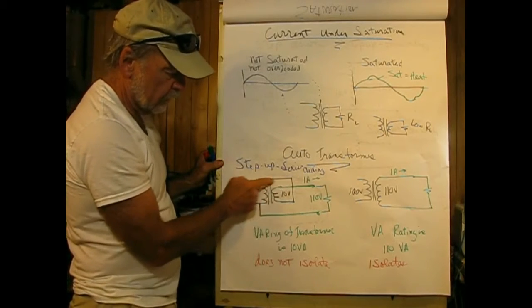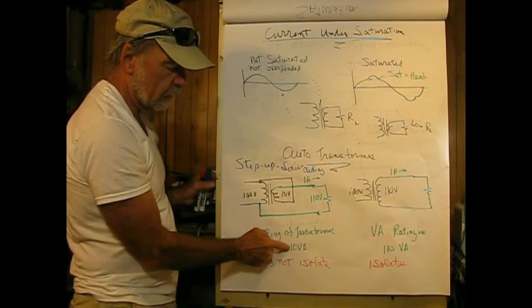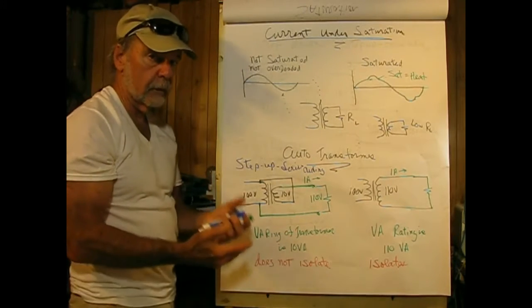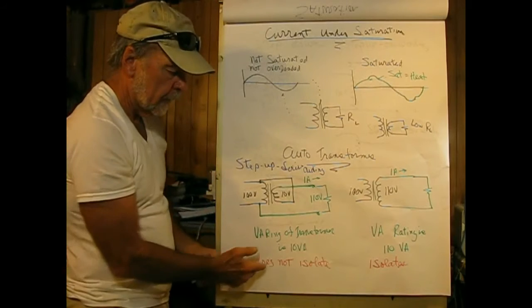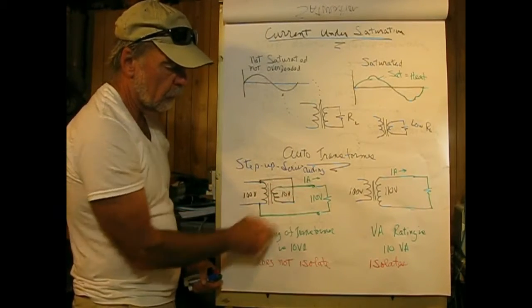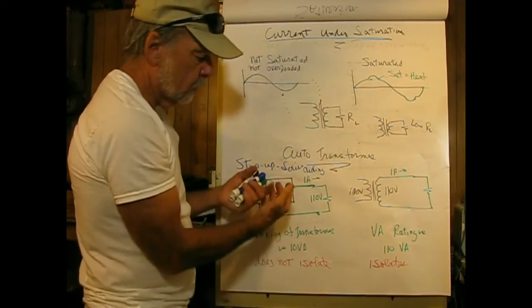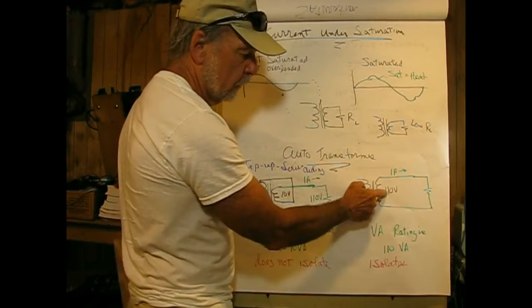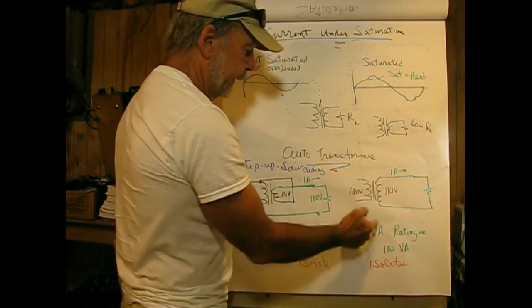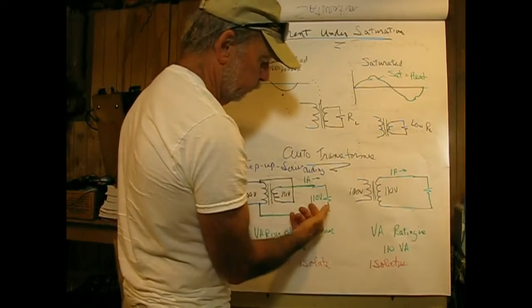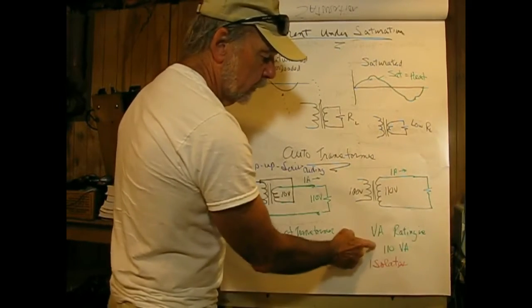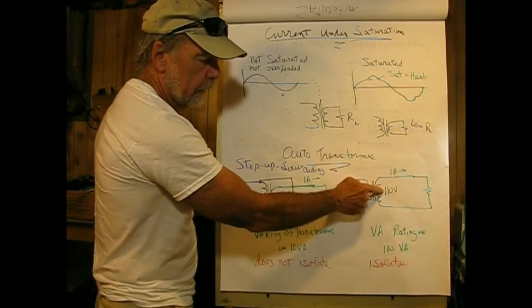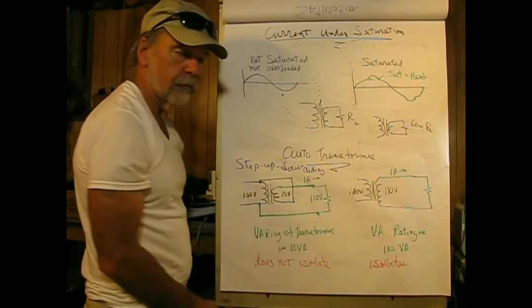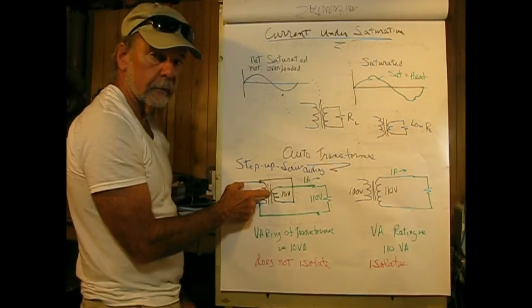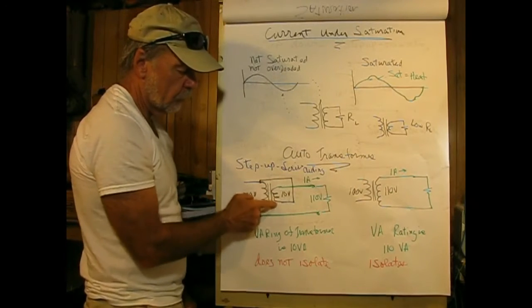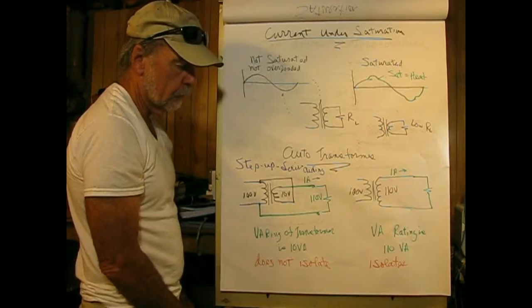So the rating of the transformer then is 10 volts and 1 ampere, which is 10 volt-amperes. Remember, VA is the correct unit of rating for a transformer. It's only 10 VA, even though there's 110 volts on the secondary. Now let's do the same thing with a regular transformer with a 110 volt secondary. Again 1 amp flows, again we have a load of 110 volts across this, but the transformer rating now is 110 VA. So this transformer is very, very large compared to the other guy, because the transformer part of the auto transformer is only producing the 10 volts. Nothing's free.